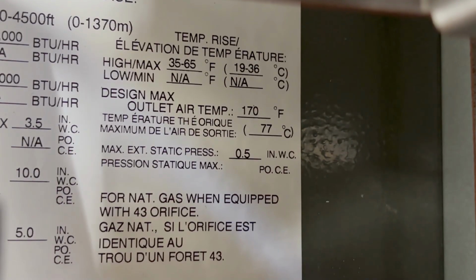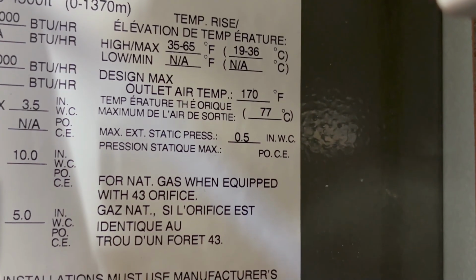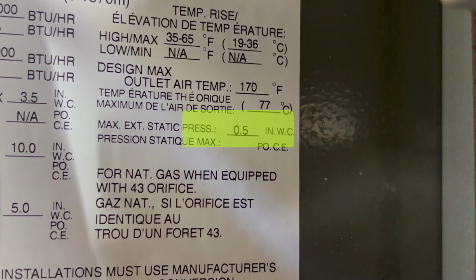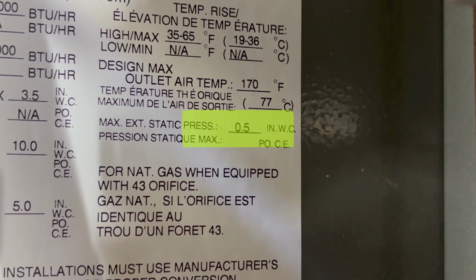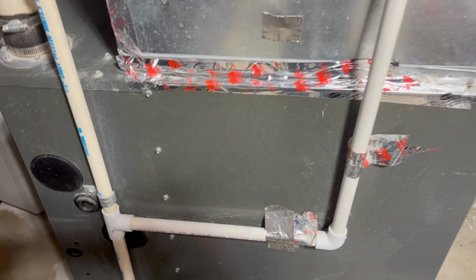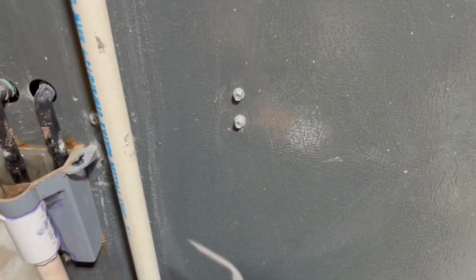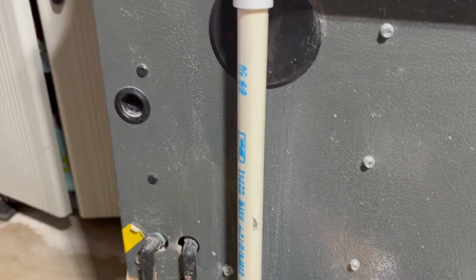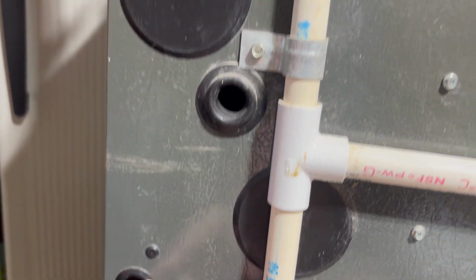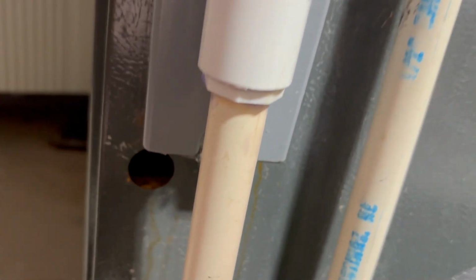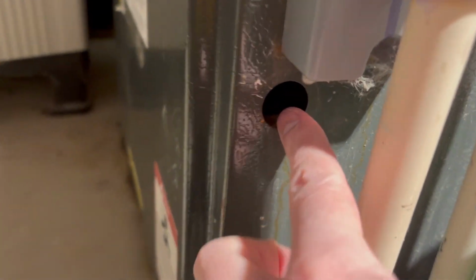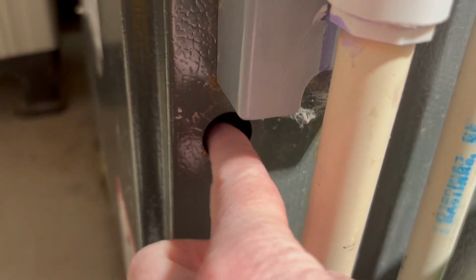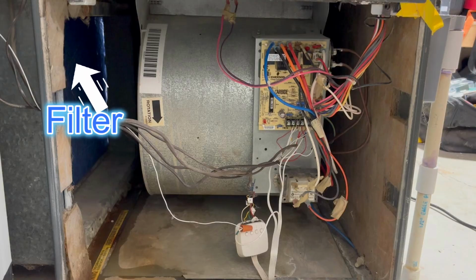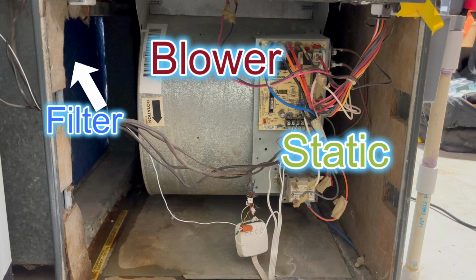And with static pressure, furnaces generally will have a rating somewhere on them, on the nameplate or in the manual, that indicates the ideal static pressure of the furnace itself. When it came out of the factory, what was it designed to operate at to achieve ideal performance? Many furnaces come equipped with ports that allow you to place the static pressure probe inside various locations. Ours has multiple ports here. The one we're going to be using is actually down here. This is on the fan inlet or the blower inlet side. So this is after the filter, before the blower. So we'll be monitoring this pressure here.